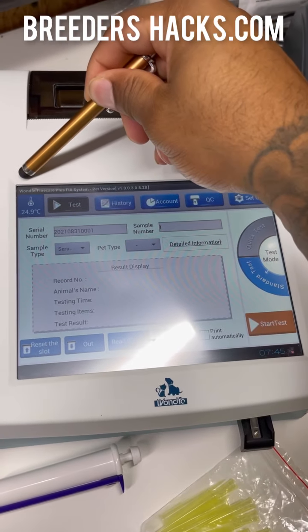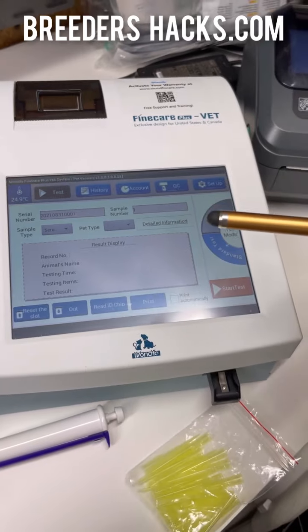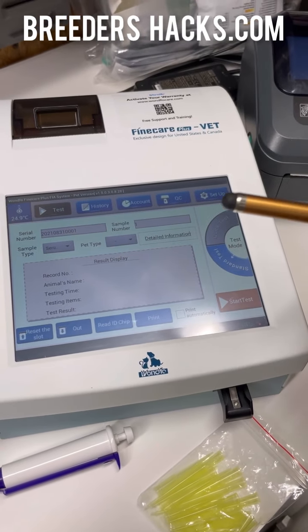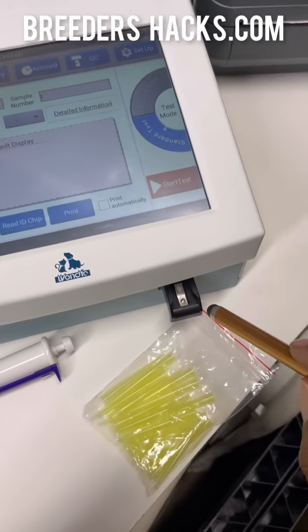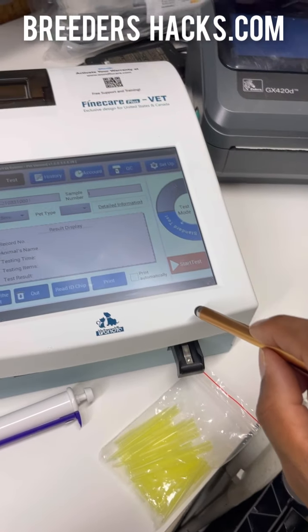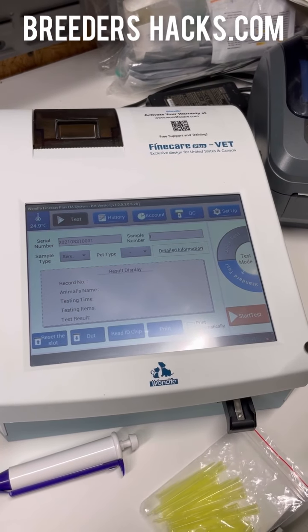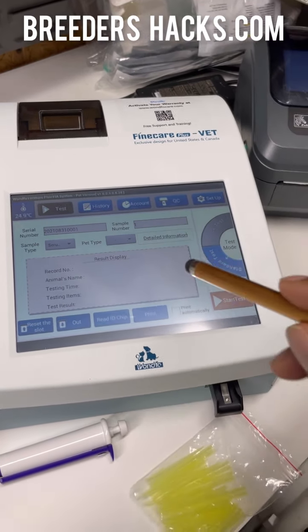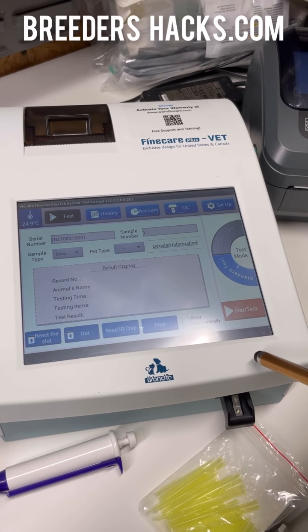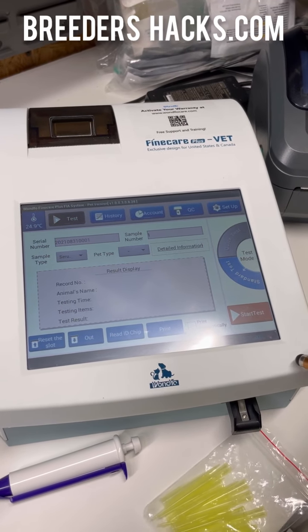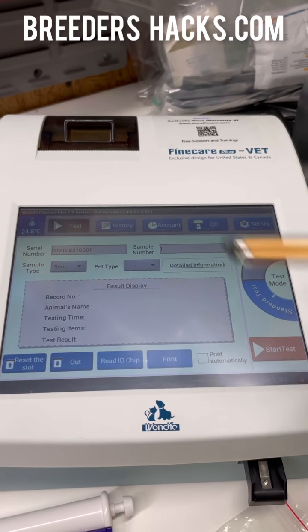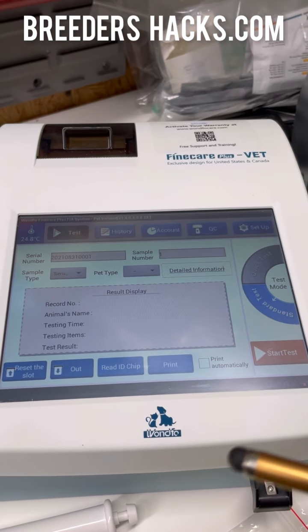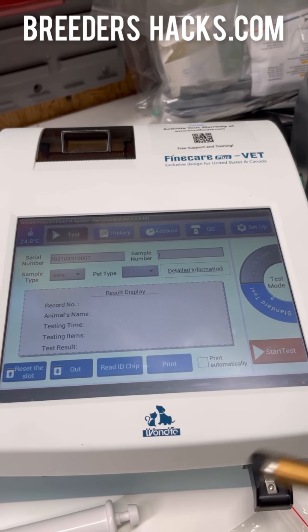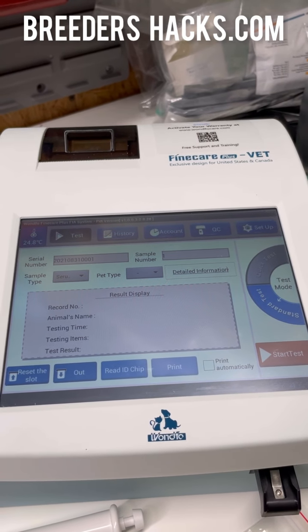Check the temperature. What I love about these machines is that it has an internal chamber that, once the test strip goes inside the machine, keeps it at a consistent temperature. Temperature is very essential and key when doing these tests so that it's accurate every time. So the first thing you're going to want to do is check the temperature. We want it to get to about 25, 26 degrees Celsius.